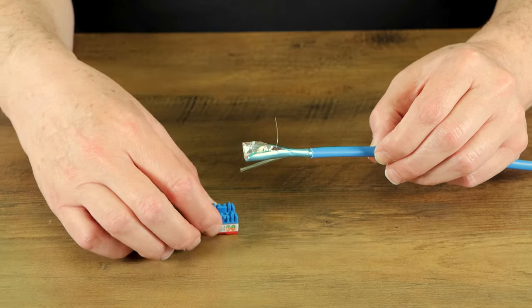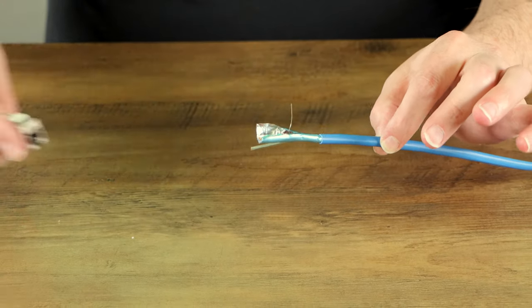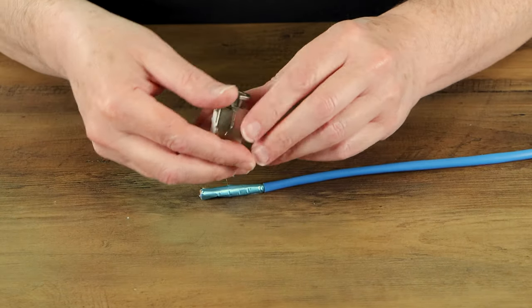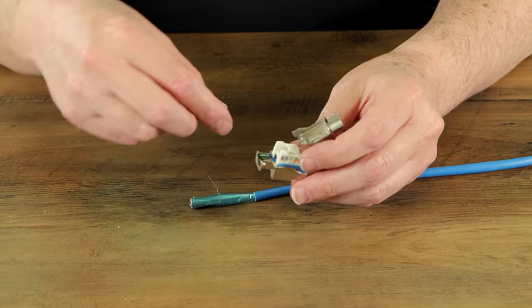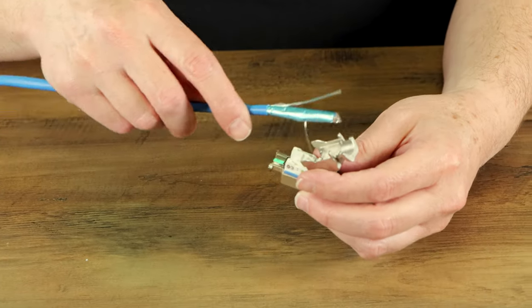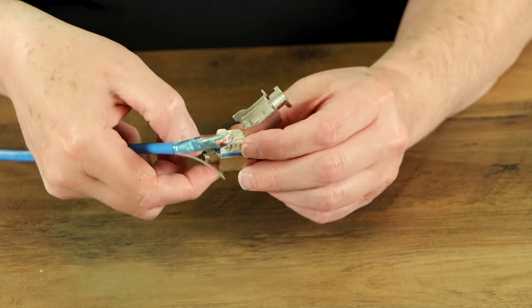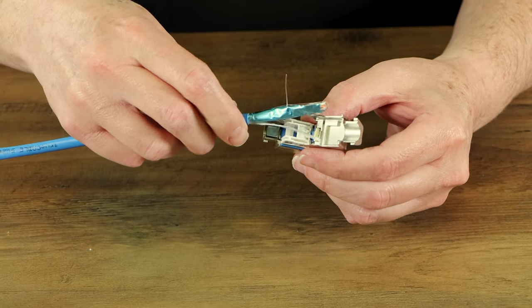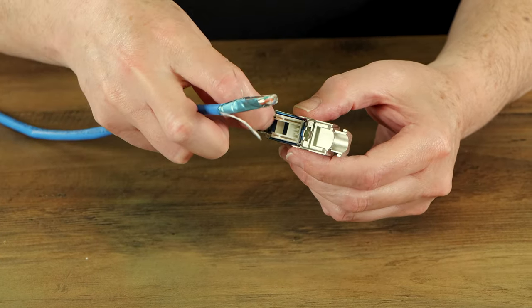So if you're going to use shielded ethernet cable, you want to use shielded connection hardware. And this is a shielded tool-less keystone jack, and the conductors all terminate into this jack. And then there's a bond and ground spring right there, which makes contact with the drain wire and the cable shield.